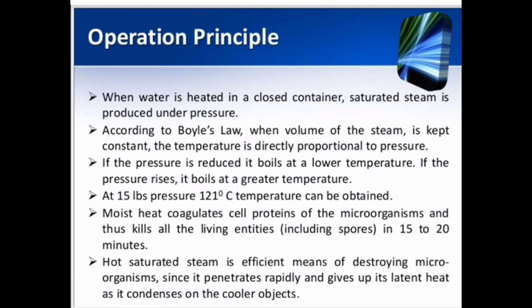At first, the water is heated in a closed container. Saturated steam is produced under pressure. Now, according to Boyle's law, when the volume of steam is kept constant, the temperature is directly proportional to the pressure. That is, if the pressure rises, the temperature rises, and if the pressure lowers, the temperature too lowers. Now, moist heat sterilization means to coagulate the cell proteins of microorganisms and thus kill all the life forms, including the spores. To achieve that, we need a minimum of 121 degrees Celsius, which is achieved only when our pressure is 15 lbs.